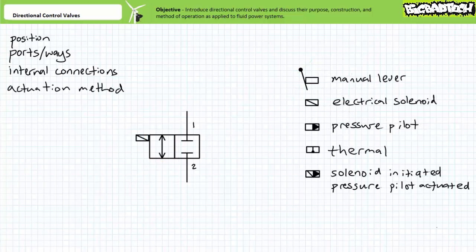Shifting a valve from position to position is the act of moving internal components like poppets, sliding plates, or spools to selectively connect or disconnect ports via the internal passageways machined into the valve body. Repositioning the movable components is known as the act of actuating the valve. Actuation methods include, but are not limited to, manual levers, foot pedals, push buttons, mechanical linkages, thermostats, electrical solenoids, pressure pilot, or a combination of these methods, like a solenoid-initiated pilot-actuated valve as is commonly illustrated for poppet-style solenoid-operated directional control valves.